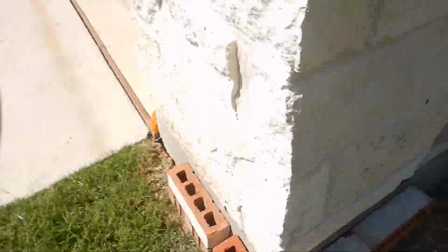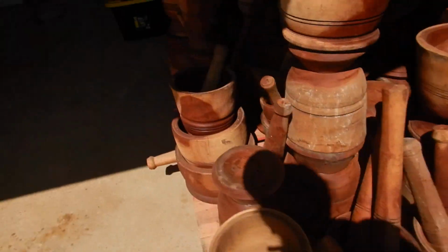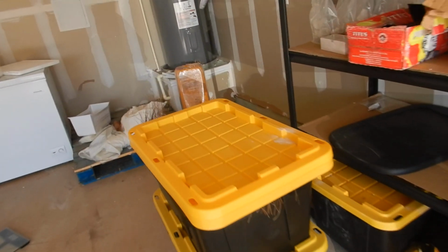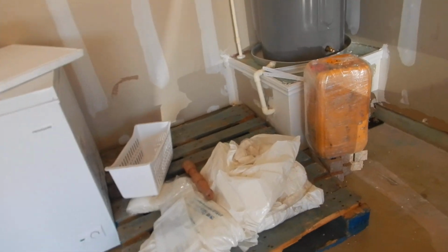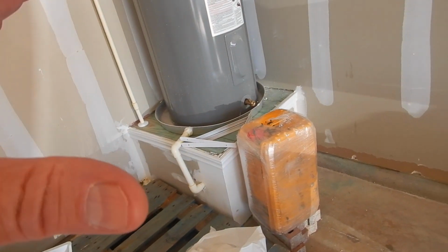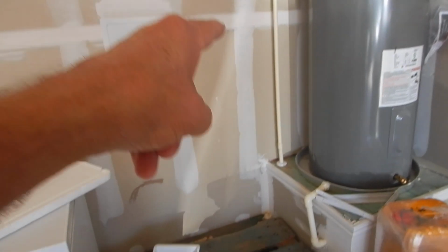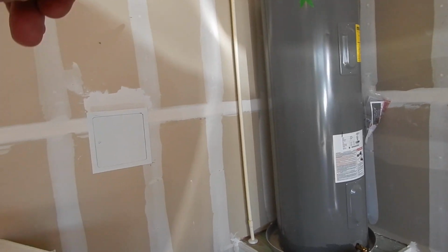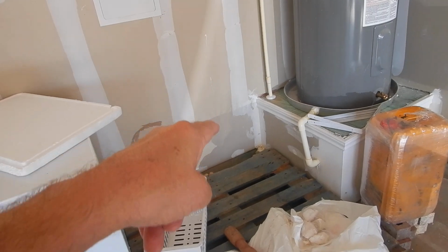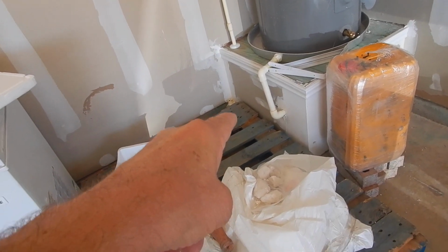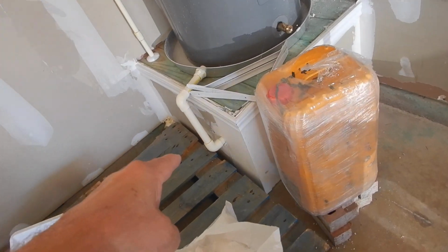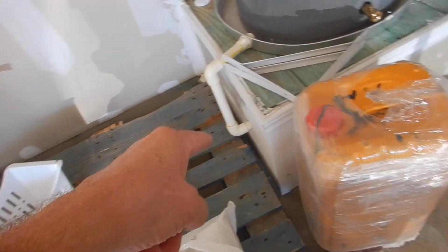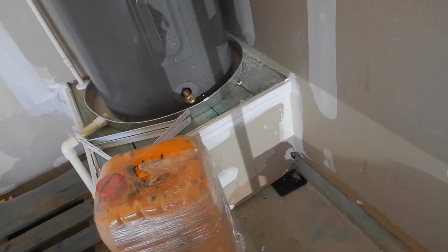We're still on the east side, and I'm going to reiterate what we just talked about. Okay, two pipes close to the water heater. Just about like what we saw on the other side of the wall. This is your water heater temperature pressure relief valve drain. And this is your safety pan drain. And this safety pan drain does not drain. It is encased in the concrete that we just talked about.